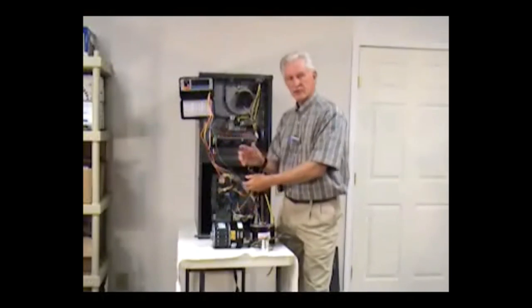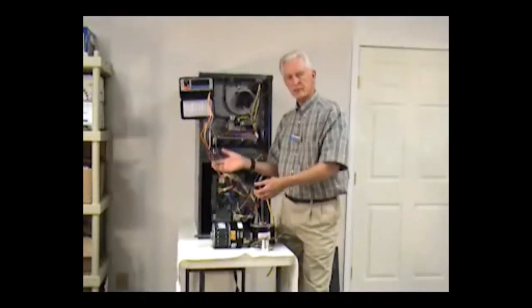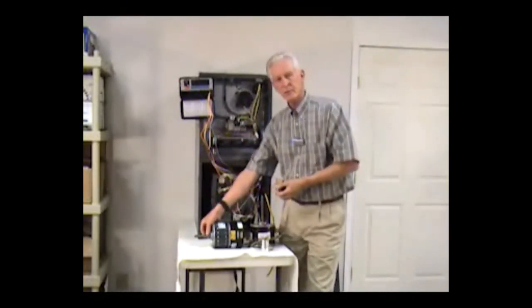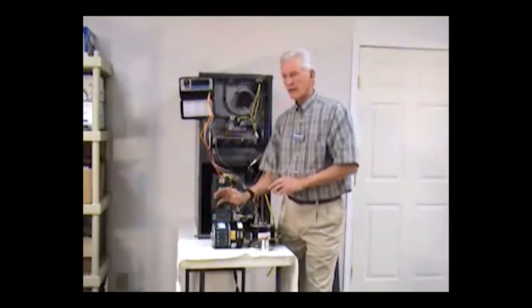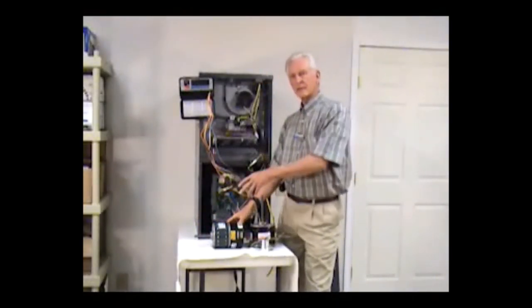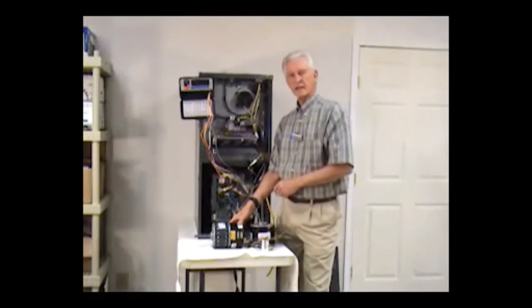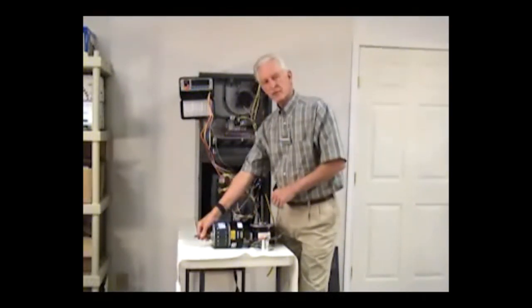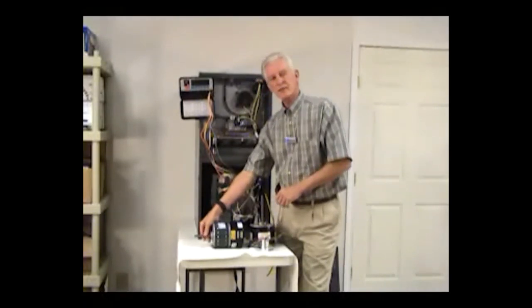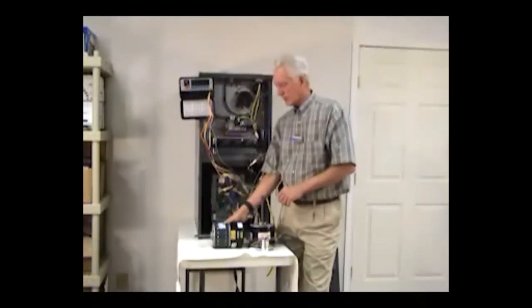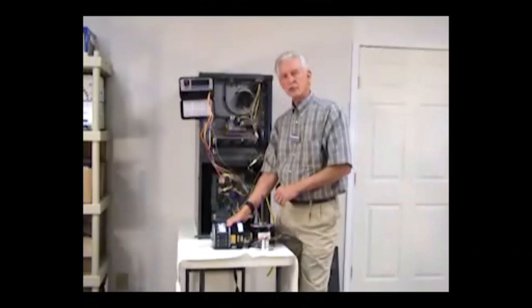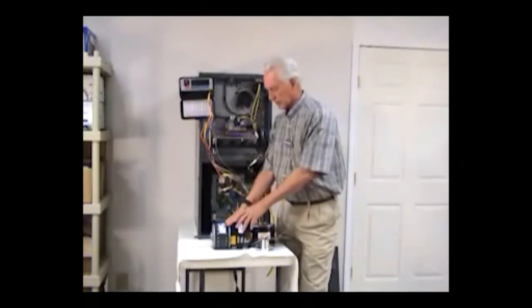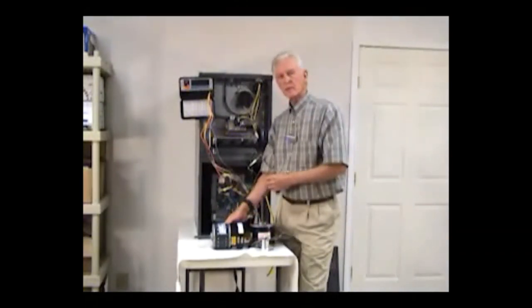And eventually it says, okay, I need to turn in this direction to deliver the air that is needed for that particular application. That is a strange phenomena that these motors have that you never find in a split capacitor motor. That rotation or trying to select the direction that it needs to go in is not a reason for you to condemn or say that we've got a motor problem.